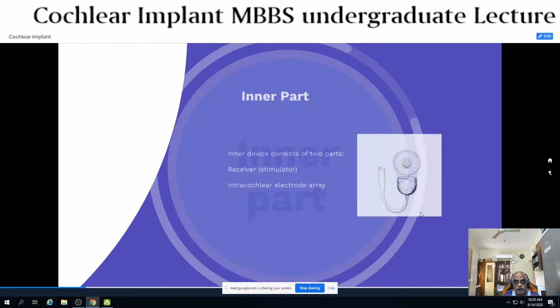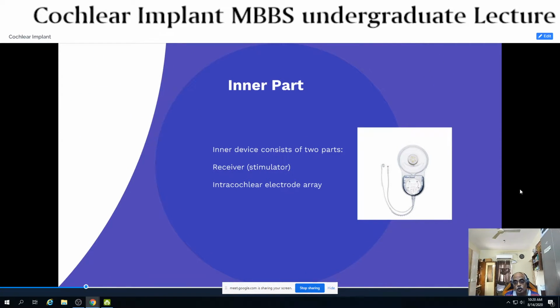So, what happens to the inner part? The inner part contains two portions. One happens to be the receiver. This receiver receives the digitalized signal from the outer part, and then it transmits these signals via an electrode array, a series of small wires containing a large number of fine electrodes, 18, 16, 24. The numbers vary according to the generation of the cochlear implant. These wires are pushed into the cochlea. So these wires stimulate the cochlear nerves directly by the impulses which are received by the receiver.